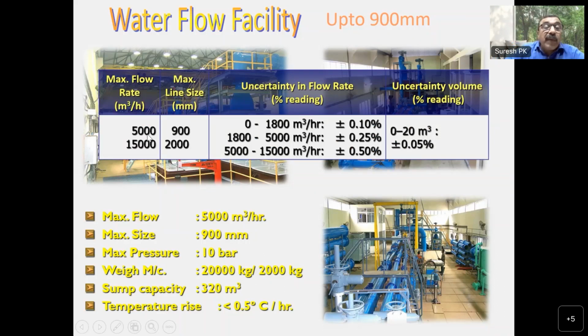So the maximum flow rate attainable is 5,000 here. The maximum line size which can be tested in the water flow lab is 900, and the flow rate with the 0.1% accuracy, you can go up to 1,800 meter cube per hour. From 1,800 to 5,000, actually it is not a gravimetric system, it is the master meter method, and the accuracy is limited to 0.25%. And 5,000 to 15,000 meter cube per hour, we have another flow system which I will show you later, which is about 0.5% accuracy.